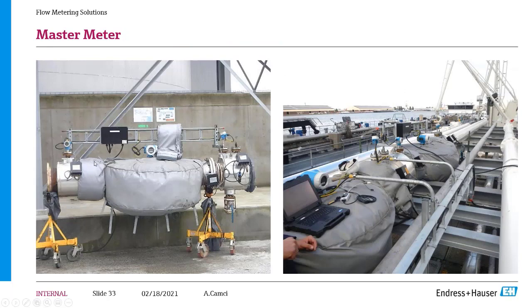The meter is calibrated with hydrocarbons on the premium accuracy range. All the transmitters are installed in this pipeline. Everything is connected to the junction box, and we even provided a quick connector once the master meter is installed for operation, so that it is easily connectable to the flow computing system to make the calculations. Here on the right-hand side you see the duty meter and master meter installed side by side, and they are reading the same flow rate.